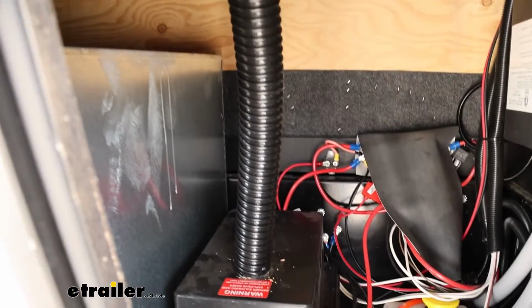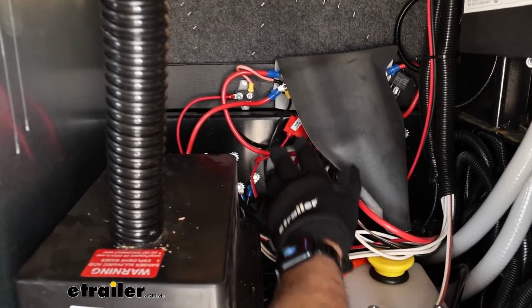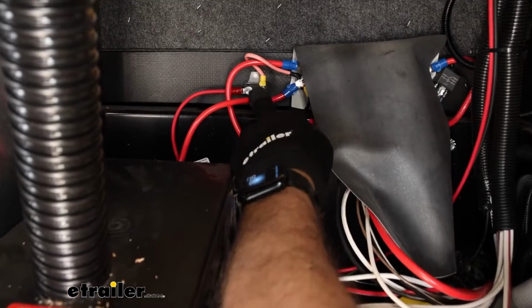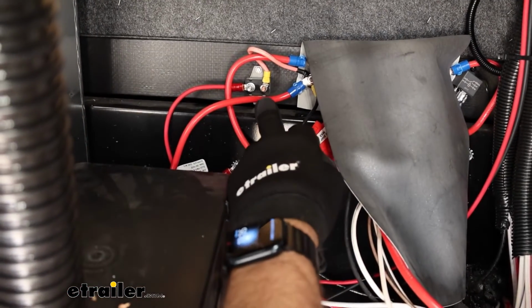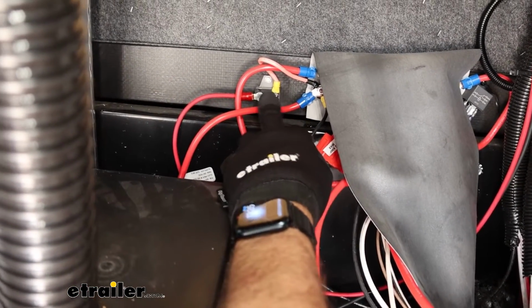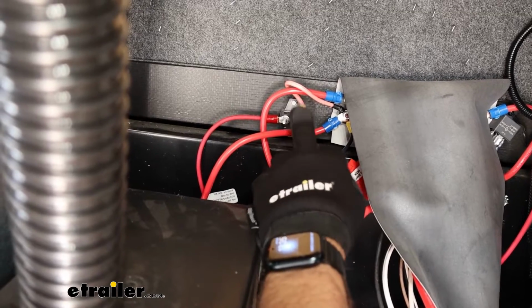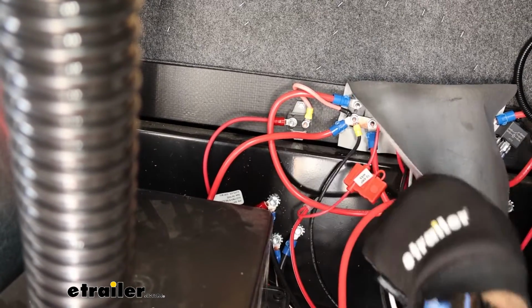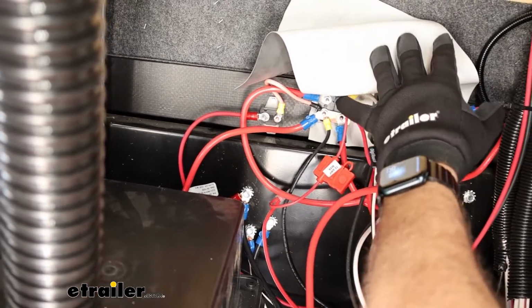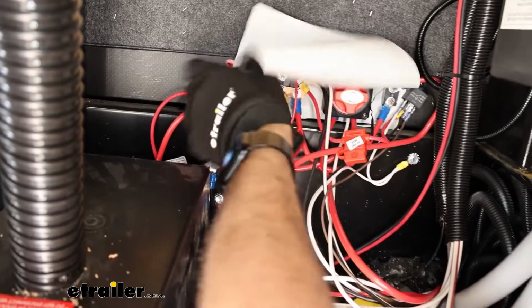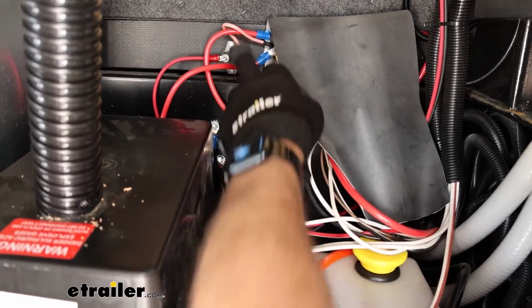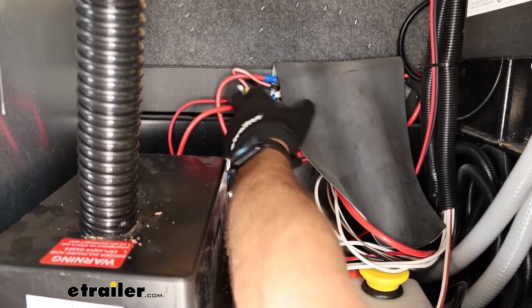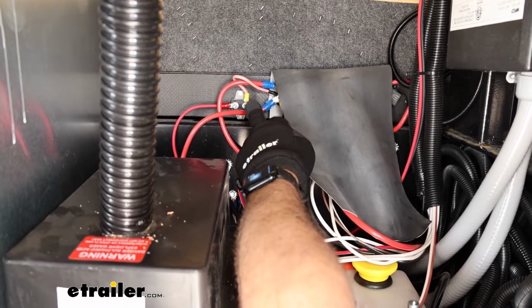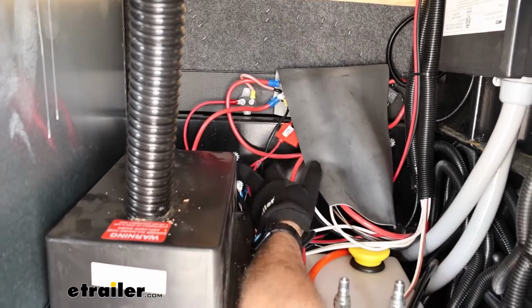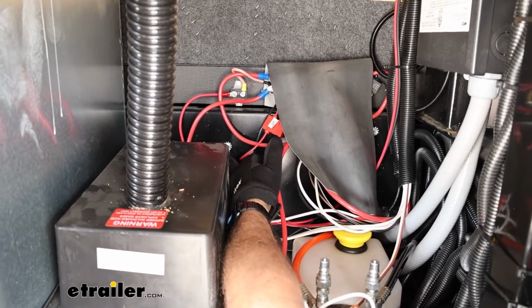Now, these systems also have a 50 amp circuit breaker that you would want to check, and that's here. Somewhere on these breakers you'll see the rated output for them. So this system should be on a 50 amp breaker. You'll see other breakers here for the camper, these are 30s. You can't tell just by looking at them, you'll have to read, and it'll be printed somewhere on one of the sides of the breaker. So check that, make sure your breaker's okay, and also make sure your ground is okay.